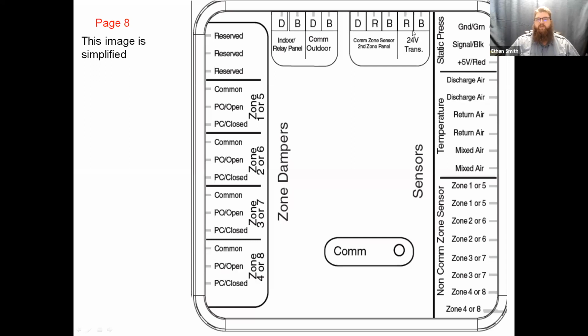Then you've got your transformer connection. Your static pressure sensor ties in right here in the top right. It is color coded to the color of the wires that come out of the static pressure sensor. Below that, you've got your discharge air temperature sensor, which I mentioned is required for the system, does have to be installed. We do have an optional return air or a mixed air sensor if you're doing something that you need those readings for. And then we've got our non-communicating zone sensors. So these would be the 2 wire thermistors, affectionately referred to as the RATs.